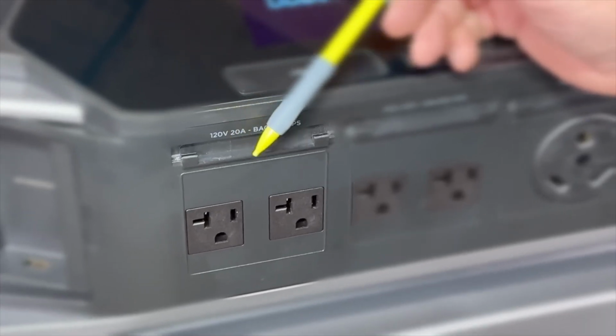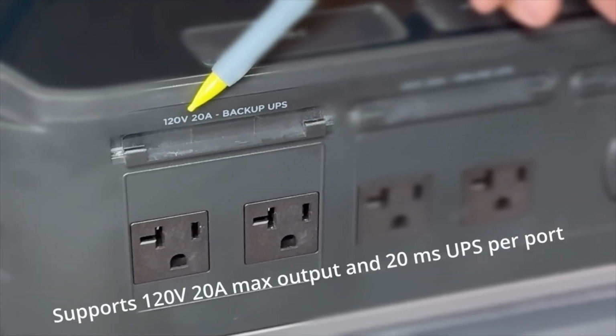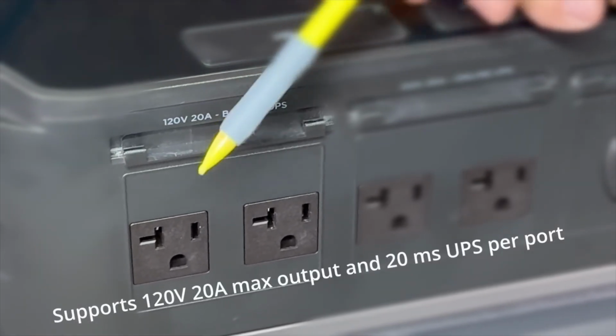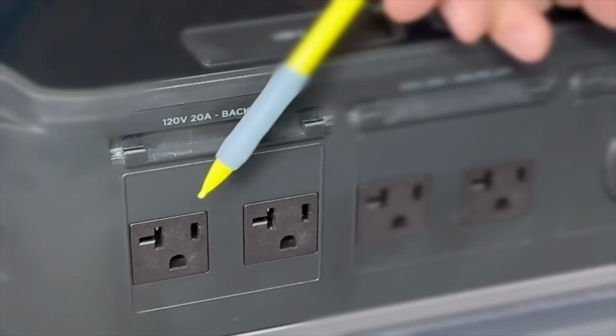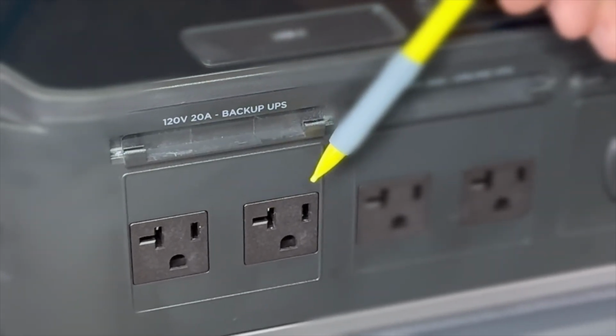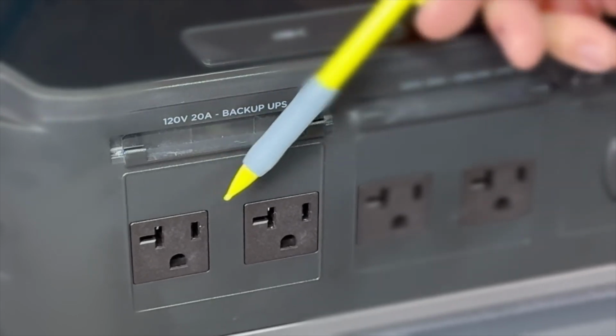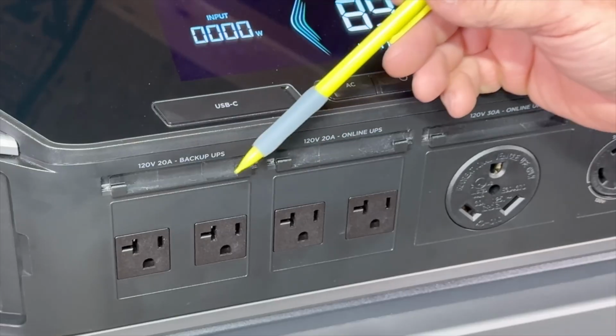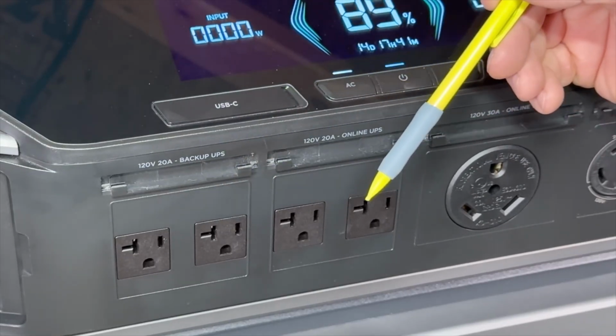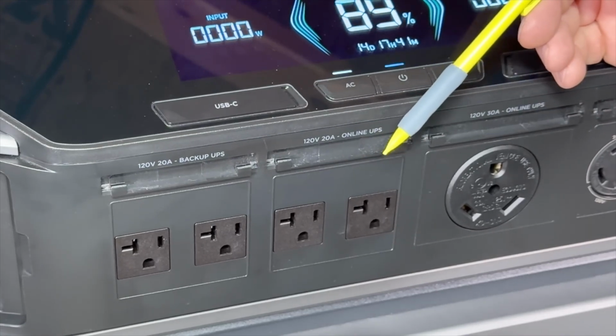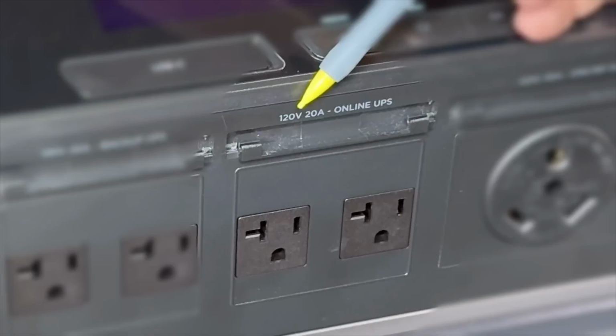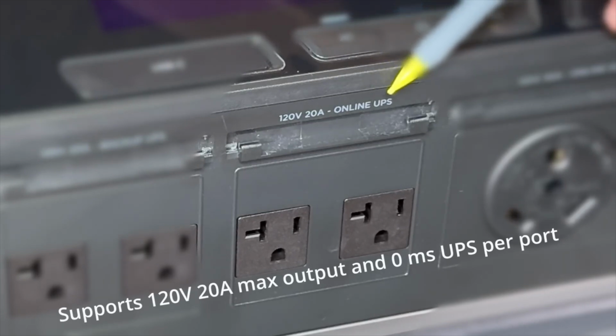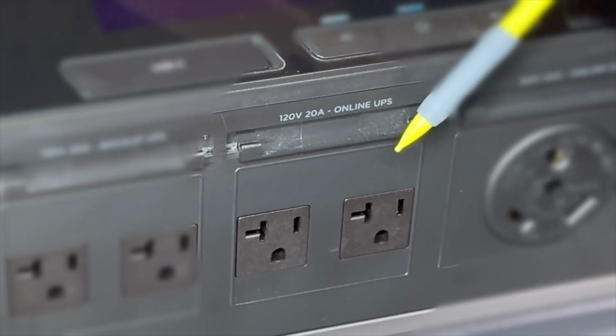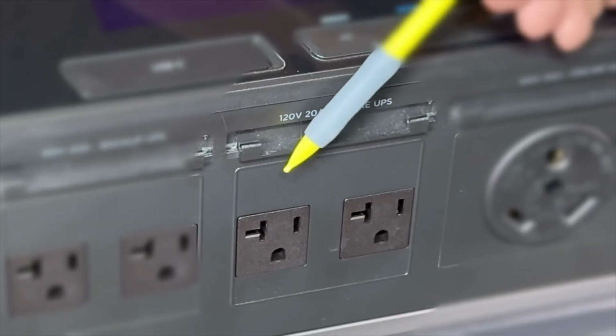Here in the front, we have two outlets that are 120 volt, 20 amp backup UPS, meaning there's about a 20 millisecond transfer speed. So if you lose power while being powered off utility, you'll have a 20 millisecond delay. Generally that's not going to affect most computers. However, if you need to make absolutely sure you don't have any interruptions, you've got a 120 volt, 20 amp online UPS. There is no delay because there is no switching - it's constantly being powered right through off the battery, so you have full backup there.